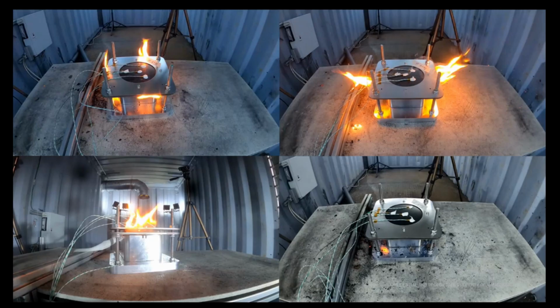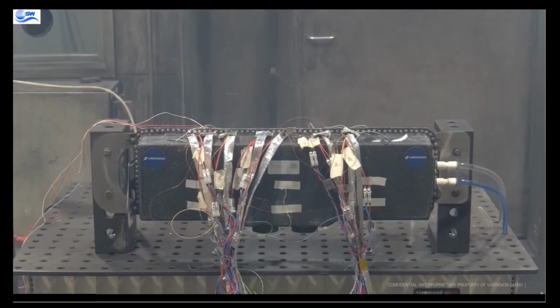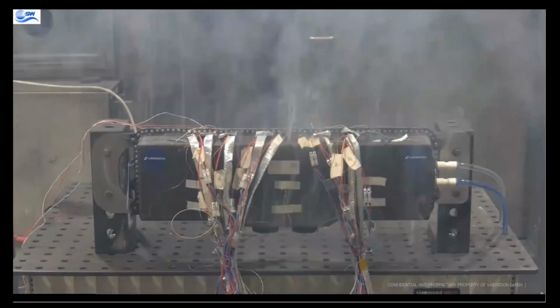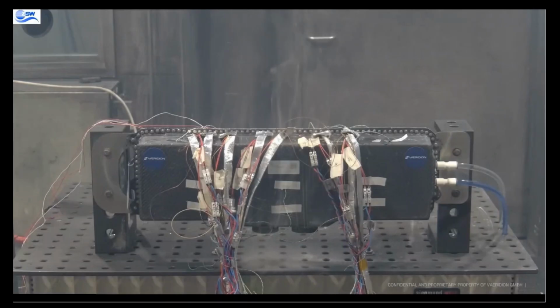We have a lot of those cells in one pack, so it needs to be designed in a way that accounts for thermal runaway. By regulations, you need to be able to contain thermal runaway within a battery pack or battery module. Here we have the older model from the battery you saw before in the pictures. We have a thermal runaway vent again, but you can see it's nicely contained within the battery module.